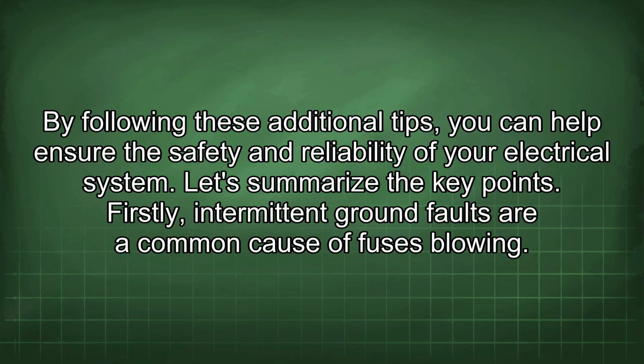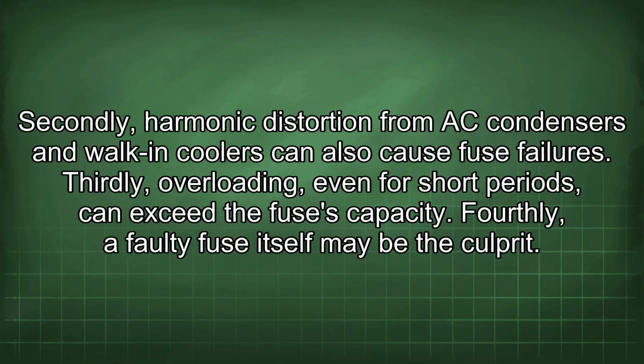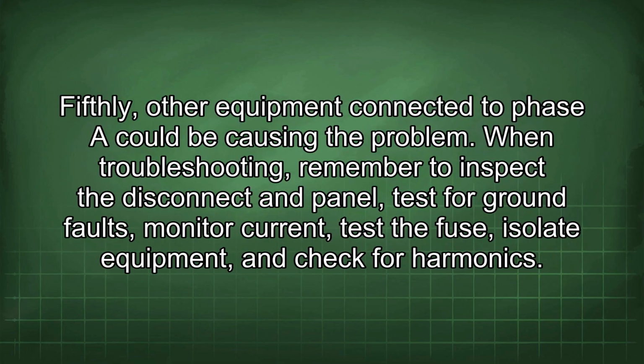Let's summarize the key points. Firstly, intermittent ground faults are a common cause of fuses blowing. Secondly, harmonic distortion from AC condensers and walk-in coolers can also cause fuse failures. Thirdly, overloading, even for short periods, can exceed the fuse's capacity. Fourthly, a faulty fuse itself may be the culprit. Fifthly, other equipment connected to the phase could be causing the problem.